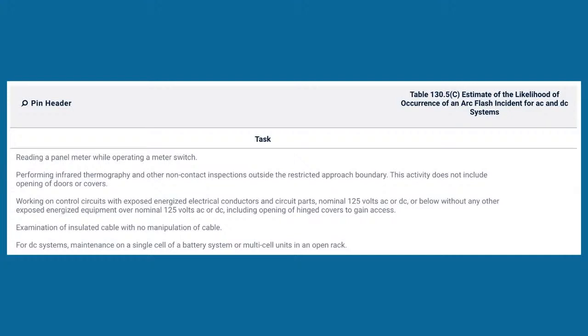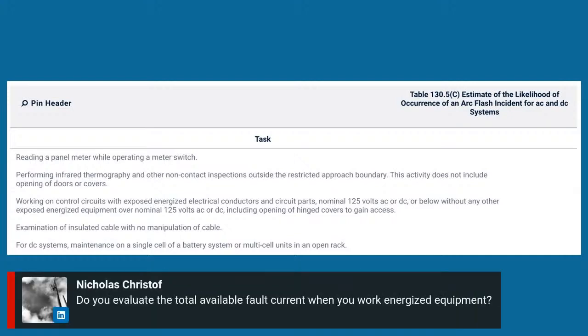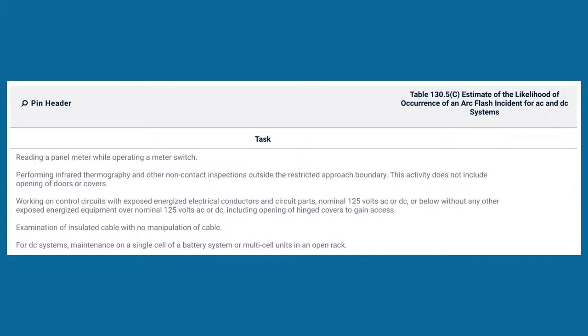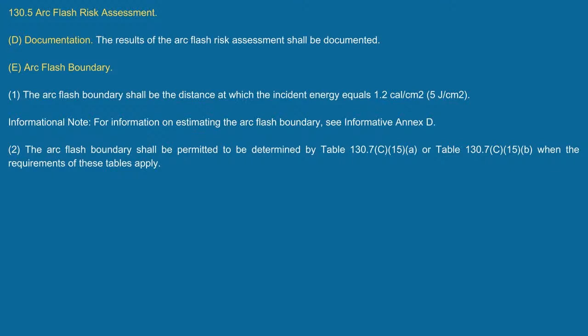Okay, so true. And you've got to have that available fault current at the equipment, or you're going to have problems applying the tables that are in there. And if that's the case, then probably the best thing to do at that time was, Nicholas or whoever it was, now you're going to have to look at doing the calculation in Annex D and get your available fault current. Yeah, and I do hear people say that they're not able to get the available fault current, but I think Bussmann has an app that you can go in and you can put in the length of the circuit, you can put in the circuit size, you can put in whatever brand overcurrent protection device you have, and then you'll get that available fault current. So great question, Nicholas. I appreciate you bringing that.